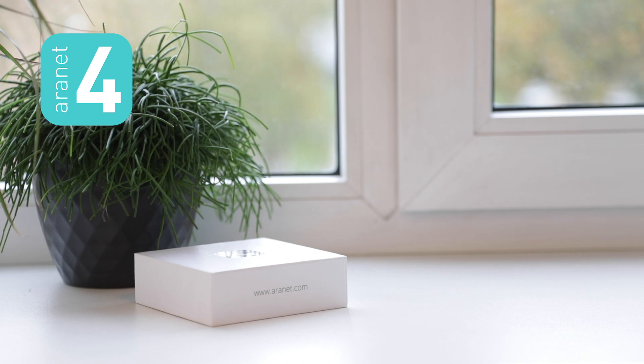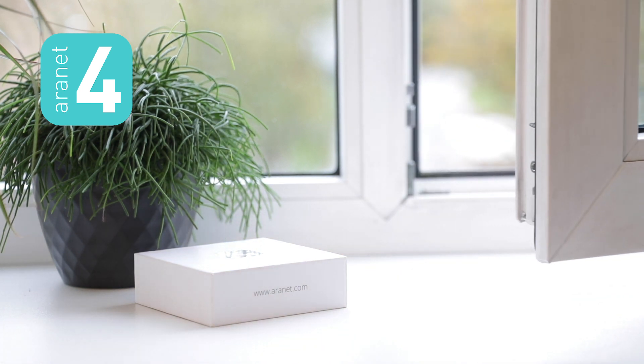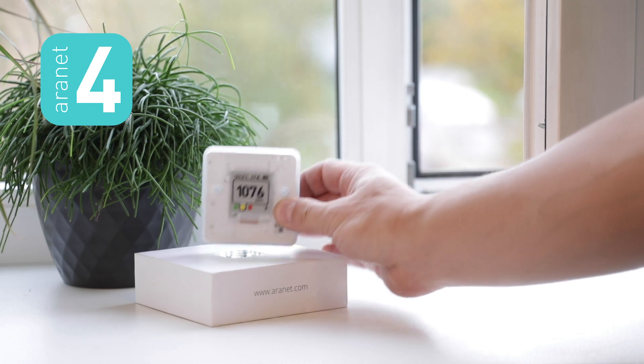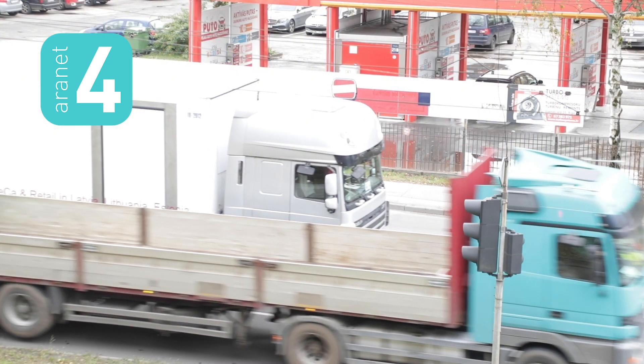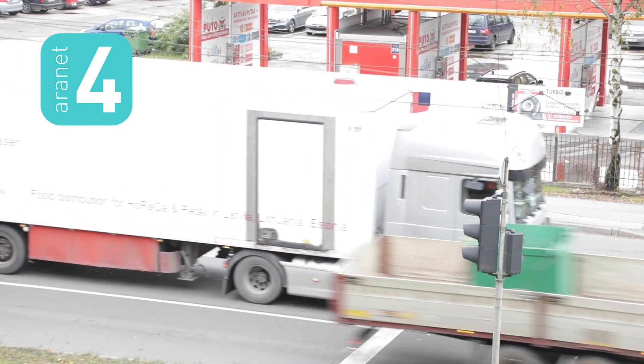First of all, make sure that you place your Aranet4 in fresh air. Pick a spot where it can be left still for 30 minutes, like near an open window. We recommend, however, that the window is not facing the street with heavy traffic, as in that case the CO2 concentration might exceed 400 parts per million.